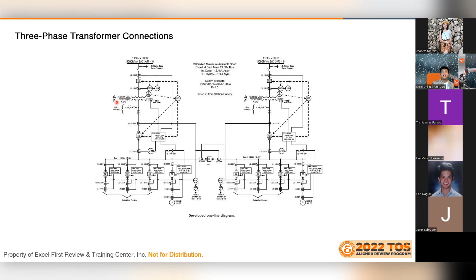If we want to zoom in here, makikita natin ito, that this one, it has a connection of transformer with delta siya, delta Y, ganyan siya, delta Y siya. Tapos siya ay 115 kV, kilovolt down to 13.8 kilovolt. Tapos the percent impedance is 8% per unit, no? Okay, so parang 0.08 per unit.